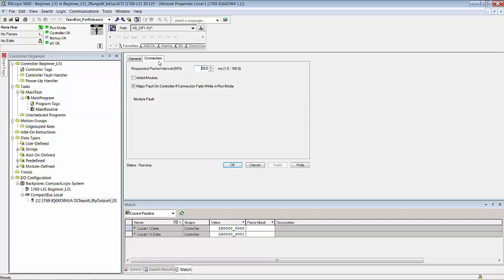That's why when I say pre-version 18, that should clue you in that it's not just a matter of them coming out with some improvements for RSLogix 5000. They have to deal with whole new chipsets. The Compact Bus Local RPI, that's right down here, that backplane right there. Requested packet interval defines the frequency at which the controller sends and receives all I/O data on the backplane. There is one RPI for the entire 1769 backplane if you are using pre-version 18 1769 L3x family processors.